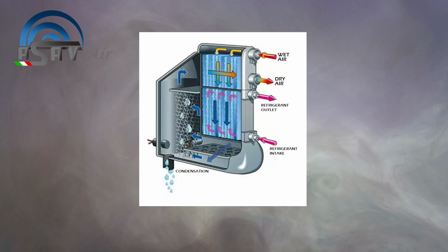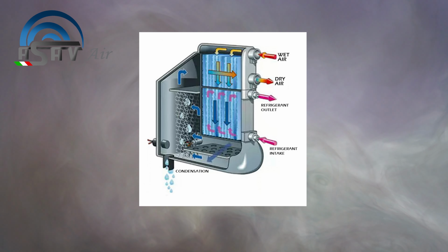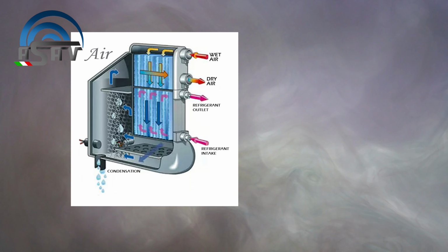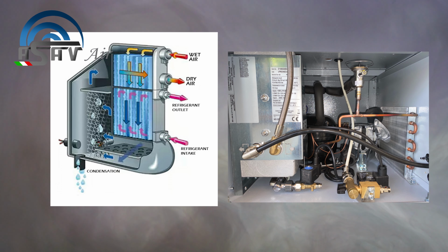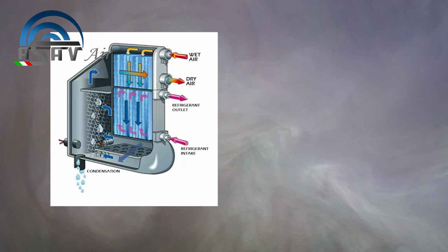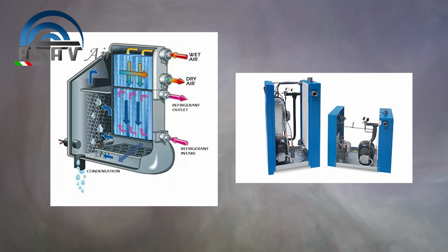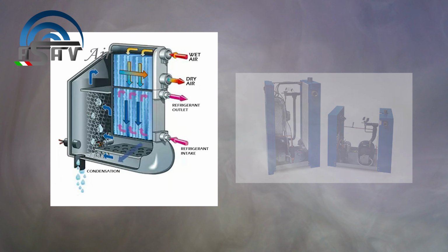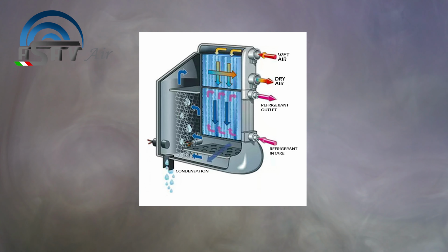The compressed air entering the unit is first cooled in an air-to-air heat exchanger. The outgoing cooled air pre-cools the incoming hot air, condensing the moisture present into liquid water that is discharged out of the system. The pre-cooled air then enters an air-coolant heat exchanger that cools it using a liquid coolant. The moisture condenses in liquid form and is drained out of the system.